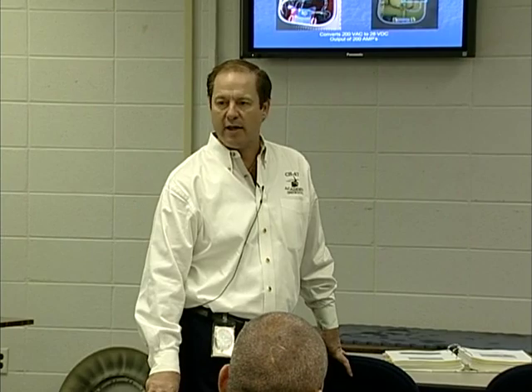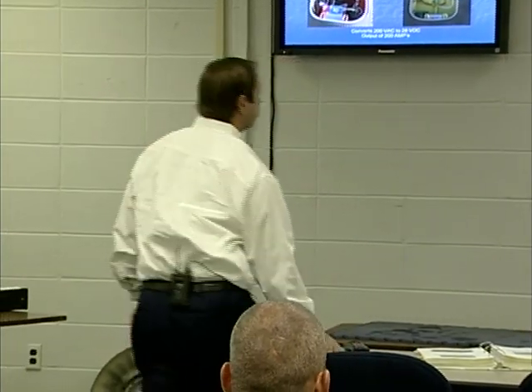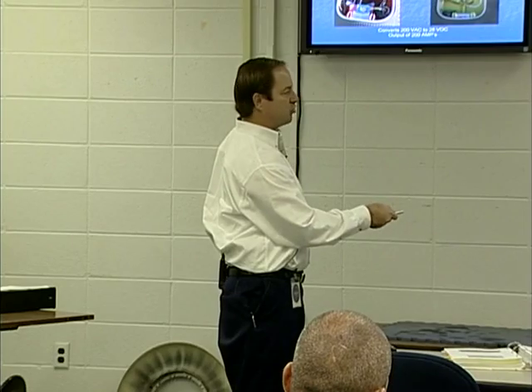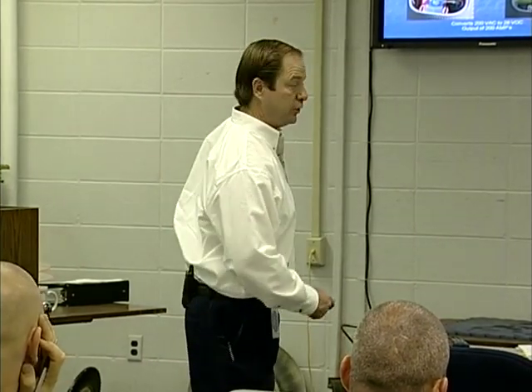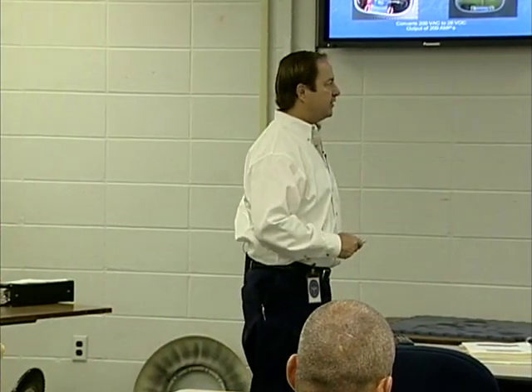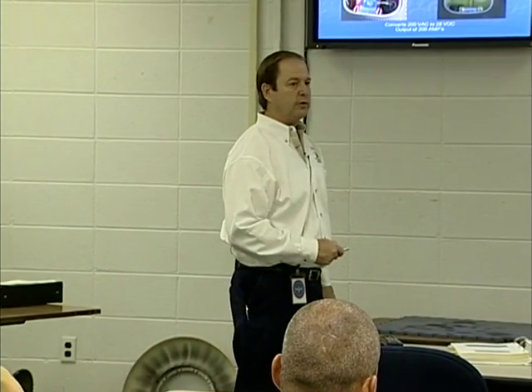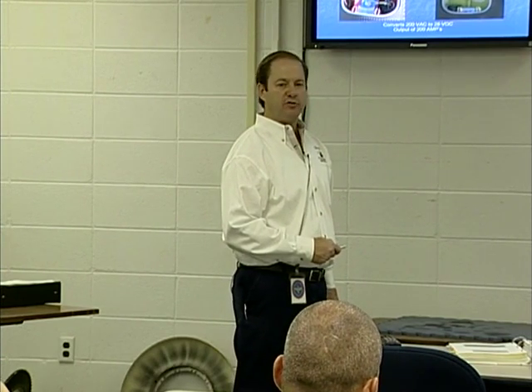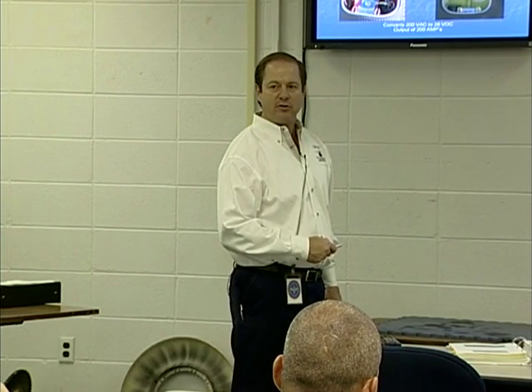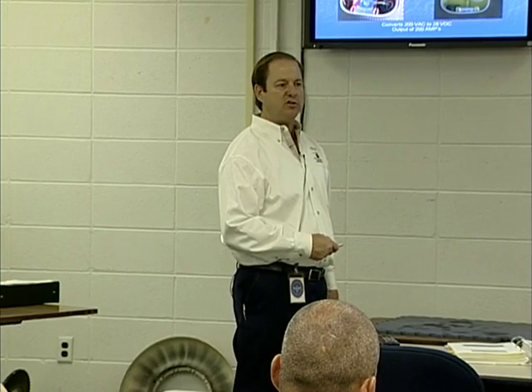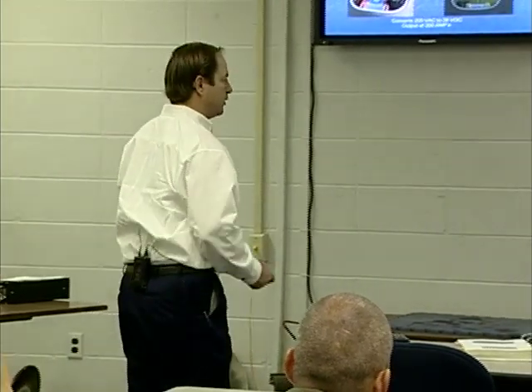Everything you need to know is right there. What do you need to know? One, will these fans turn? You'll commonly see people blow into them to make them turn—that's verifying the fans are turning or free to turn. The next thing to check is for looseness of electrical connections. But if the transformer rectifiers are powered up, if any of those electrical connections are loose, there's going to be some arcing and sparking going on. So there's nothing you have to shake at this point—that's as long as they're powered up.